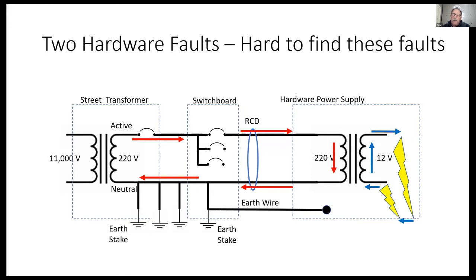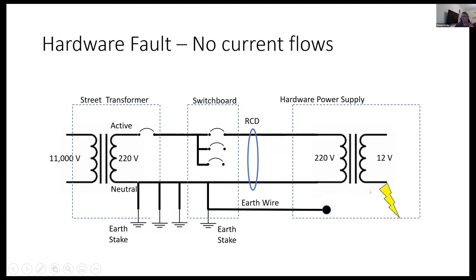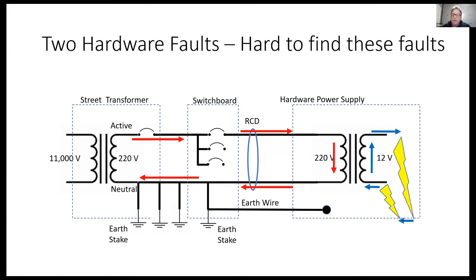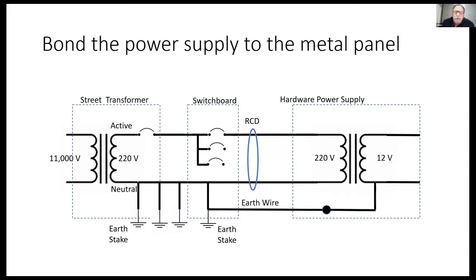A system on the secondary side where you've got it floating, you can have faults and they have very little effect on the primary. So one of the things you can do, not for circuit function but for fault finding, is take the 12 volt supply, like John's 12 volt DC, and connect the 12 volt negative to the metalwork. The advantage is that when you have a fault, the first fault, your circuit protection, like the power supply, might shut down through its current limiting, or you put a circuit breaker or a fuse and it'll blow.